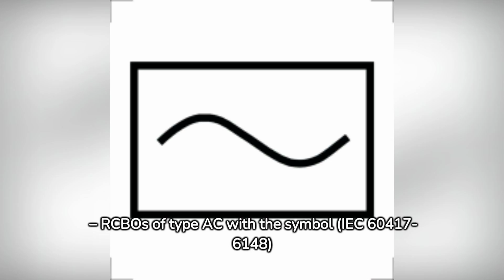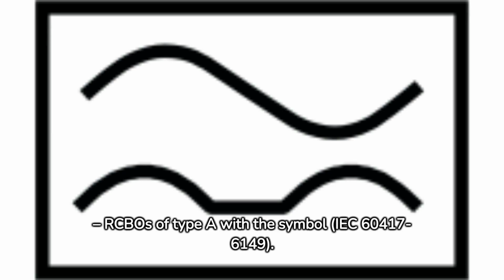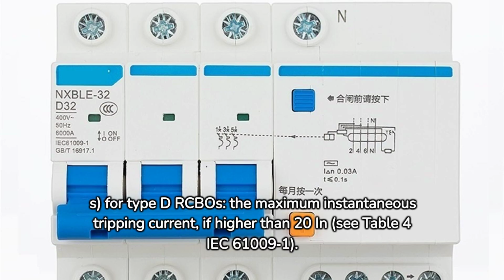RCBOs of type AC with the symbol IEC 60417-6148. RCBOs of type A with the symbol IEC 60417-6149. S. For type D RCBOs, the maximum instantaneous tripping current, if higher than 20 In, see Table 4 of IEC 61009-1.